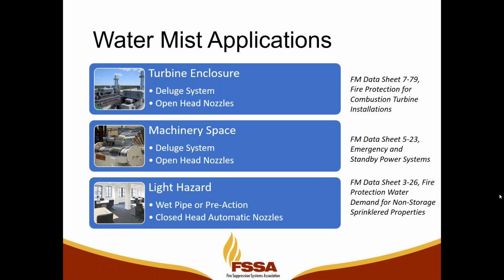If you want to get into detail about the protection scheme that FM recommends for each of these hazard types, go to those data sheets and read them. They'll give you diagrams that talk about nozzle placement, and they will tell you which parts of the hazard need to have nozzles present to protect them, and really just a great source of information about how to protect the space. Another huge water mist application is obviously light hazard.